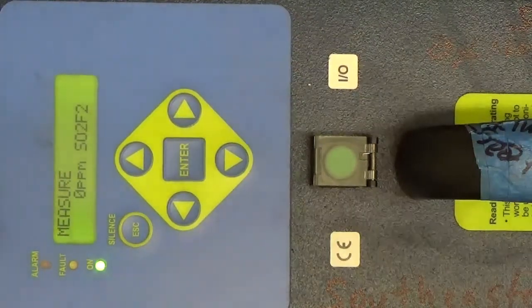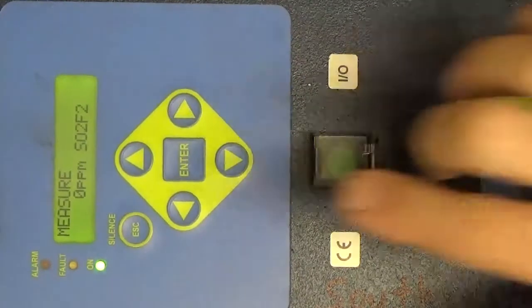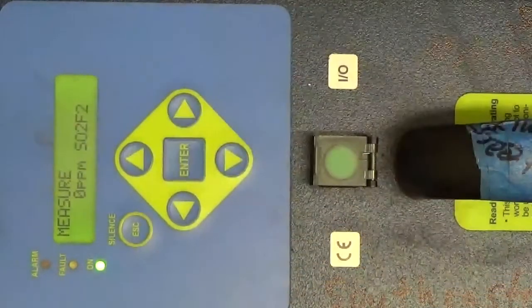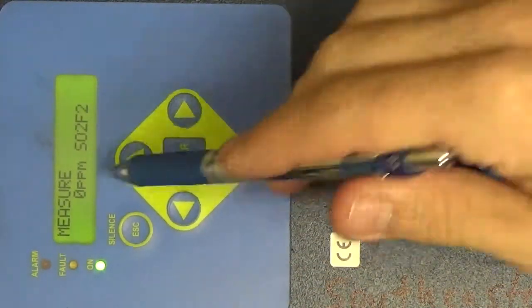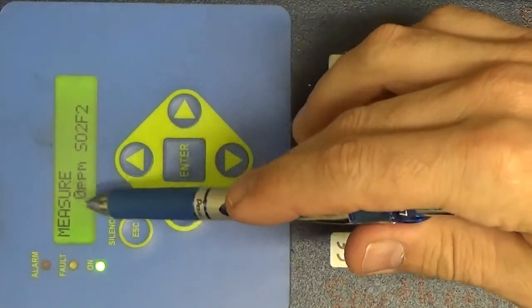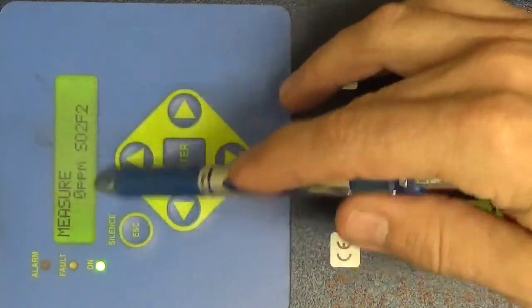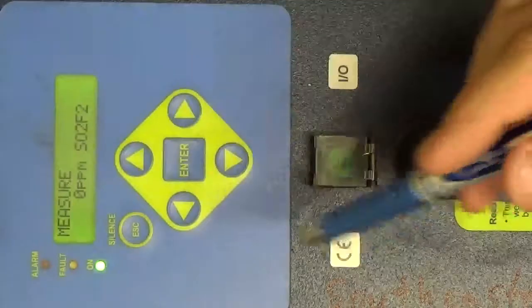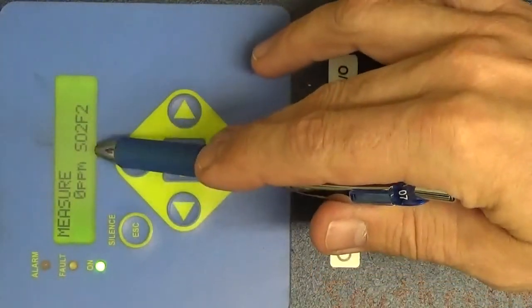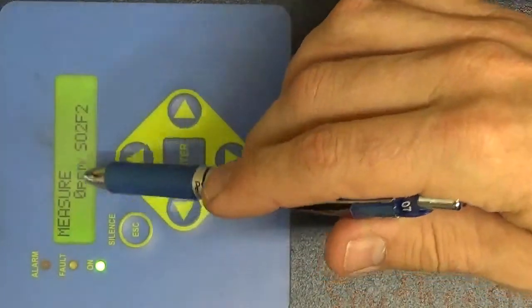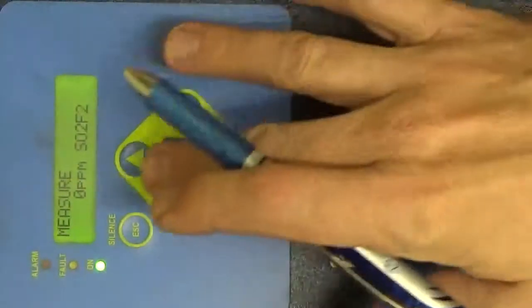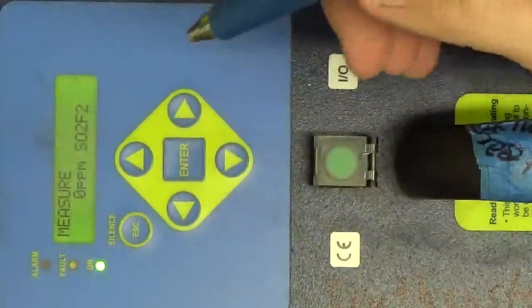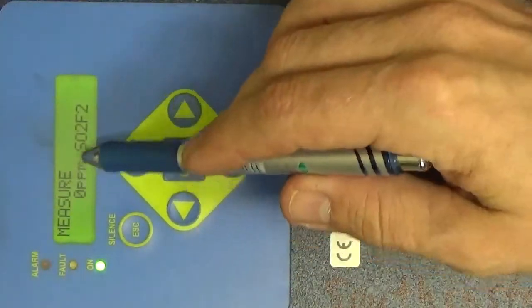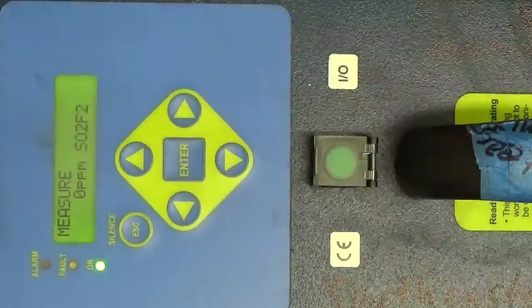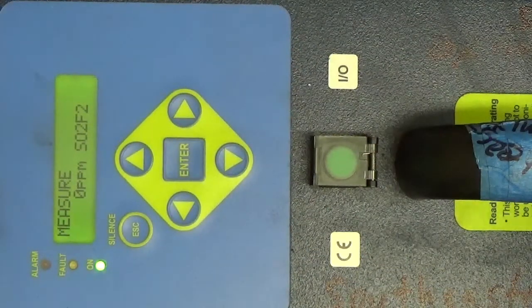Alright, once the unit starts up and it's in the measure phase, let me get my pen. It's in the measure phase. Just confirm that if you're in fresh air, you're getting a 0 ppm, we're not getting 3, 4, 5, that you're not getting numbers that you wouldn't expect to see. So first thing you do is just, again, a quick visual. Is it doing what you expect it to do?